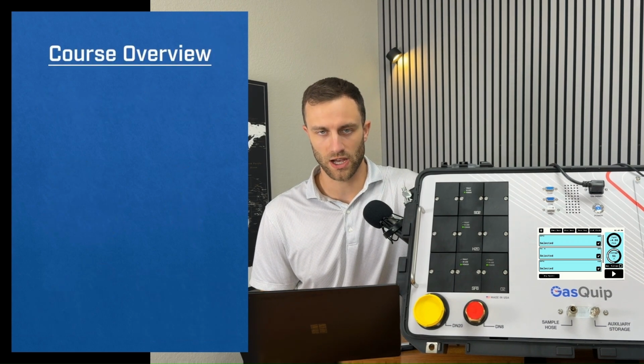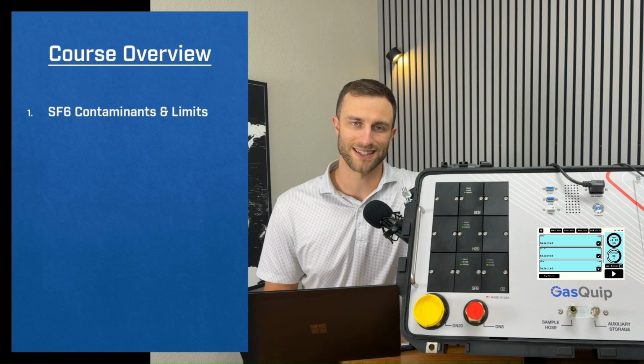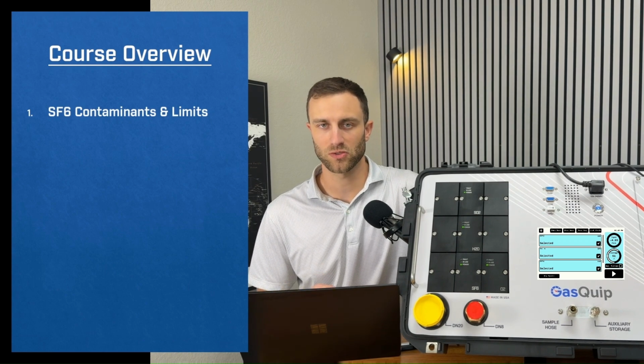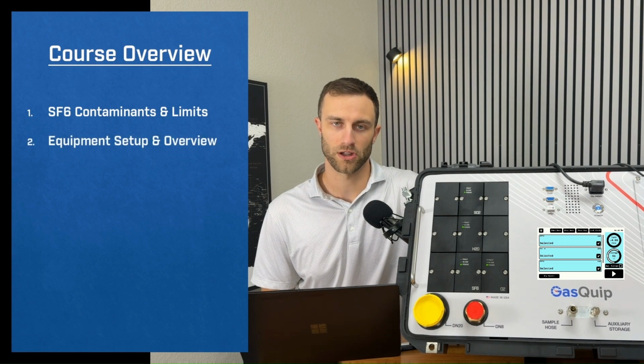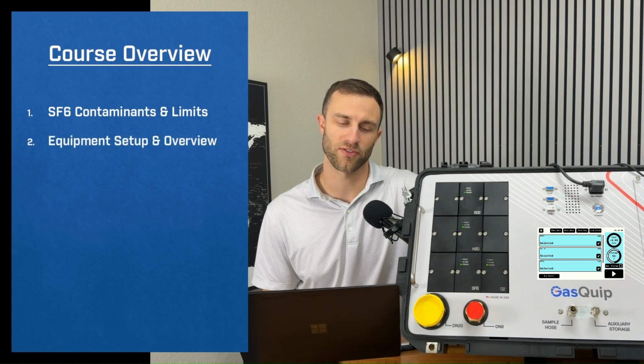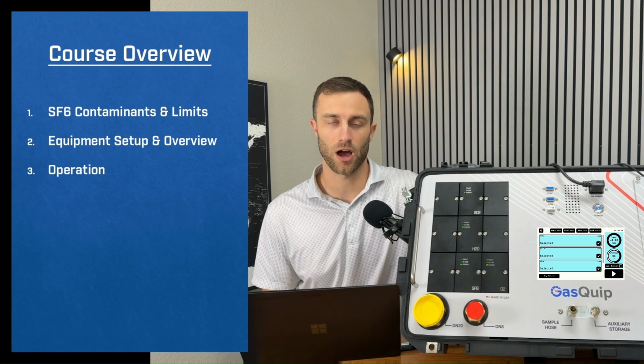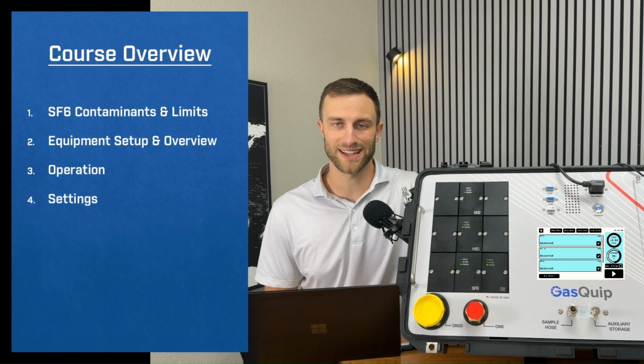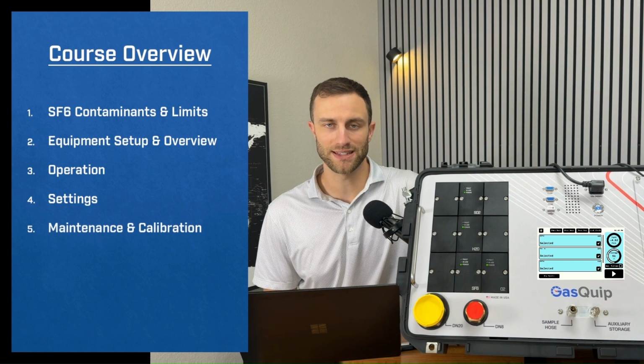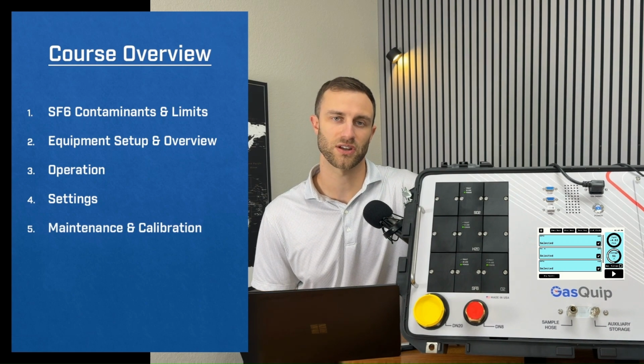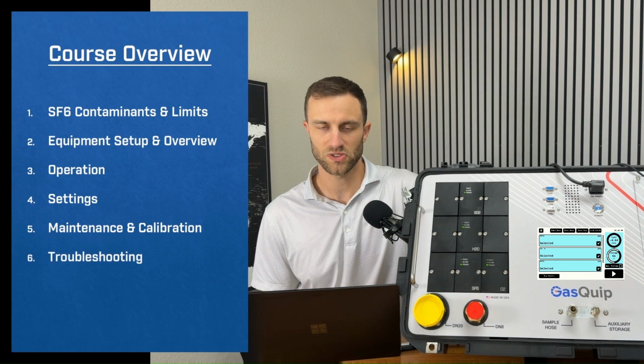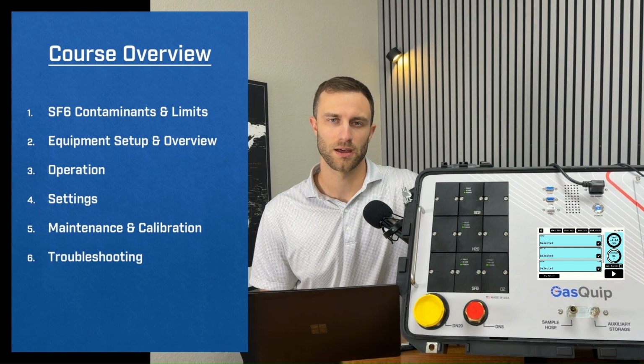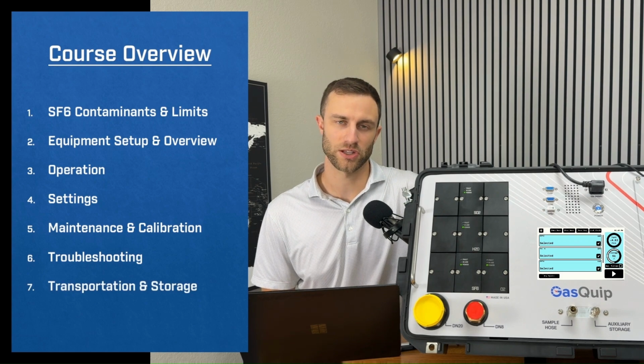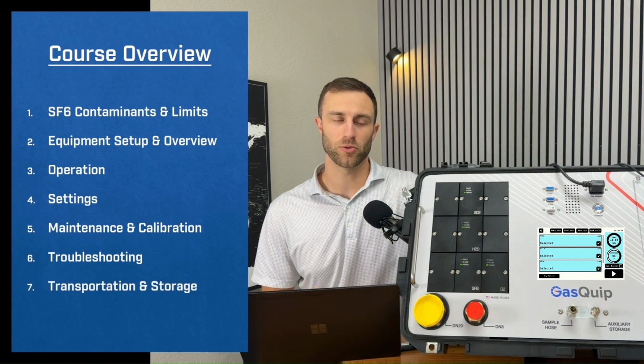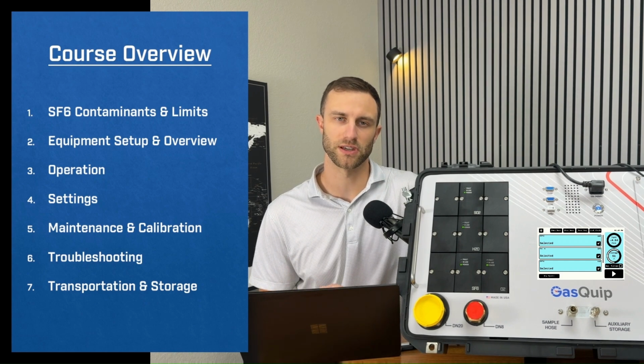So on the course side, we're going to talk about SF6 contaminants and limits and what to expect while testing. We're going to get into the equipment setup and overview for the Flex, talk about how to operate the Flex, some of the settings to look out for, the maintenance and calibration of the Flex and other similar analyzers, some typical troubleshooting methods that you can try, and transportation and storage. Now, this training will be unique to the Flex, but it should apply broadly speaking to many different analyzers that are out in the field today.